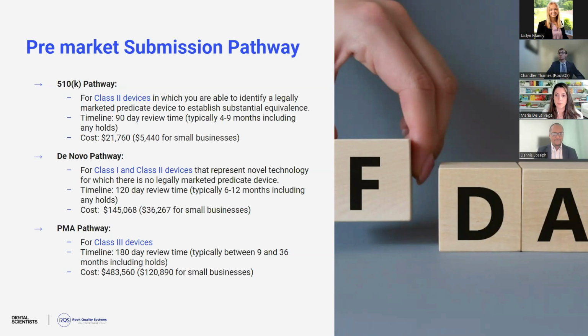And because of this more extensive review, the cost goes up as well. So $145,068. For that small business designation, it drops to $36,267, but this is 6 to 7 times the cost of the 510K pathway. So it's definitely recommended to try to find that predicate device and move forward through that pathway.